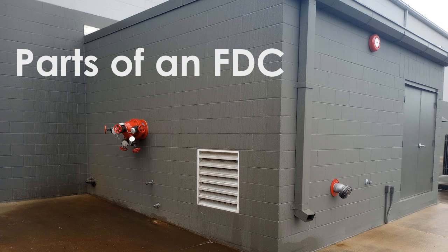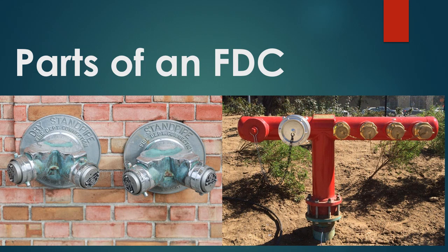Fire department connections can come in a lot of different shapes and sizes. Oftentimes it is a Siamese, like you see on the left. That's the body or the housing of the Siamese. There'll typically be a clapper valve on the interior. It has a swivel, which is a female. Your male coupling will go into this swivel. These are plugs. They're specifically Knox plugs that require a key to open up.